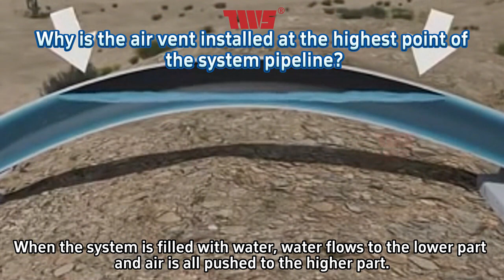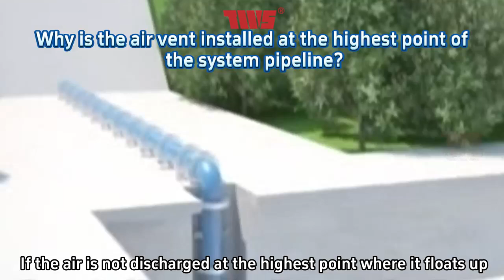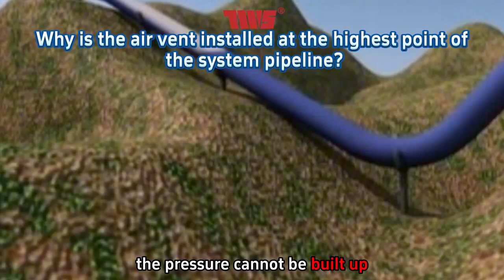When the system is filled with water, water flows to the lower part and air is all pushed to the higher part. If the air is not discharged at the highest point where it floats up, the water flow will be intermittent. The pressure cannot be built up.